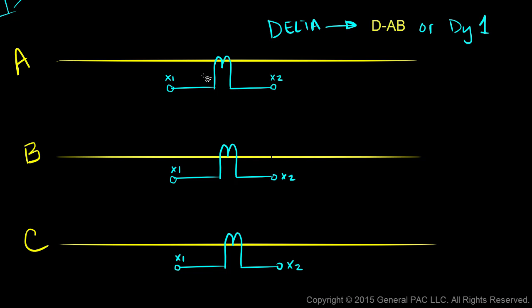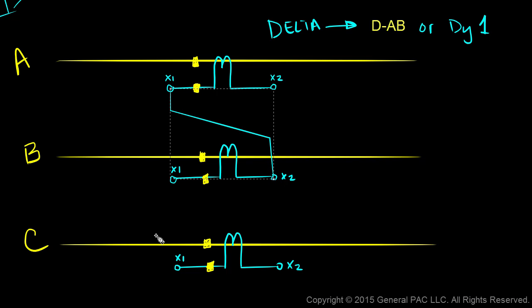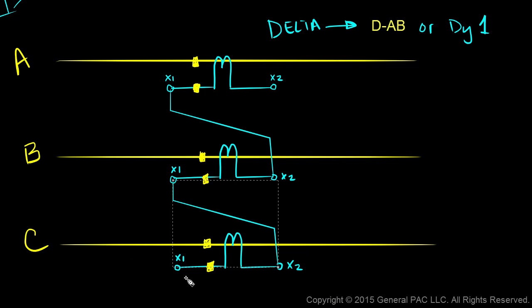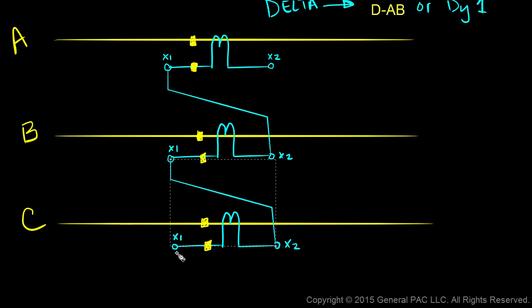Before showing how the Delta is connected, let's define the polarity marks — I'll assume the polarity marks are on this side. To connect the 3 CTs in Delta: we take the polarity side of Phase A CT and connect it to the non-polarity side of Phase B CT. Similarly, we take the polarity side of Phase B CT and connect it to the non-polarity side of Phase C CT. And lastly, the polarity side of Phase C CT connects to the non-polarity side of Phase A CT.